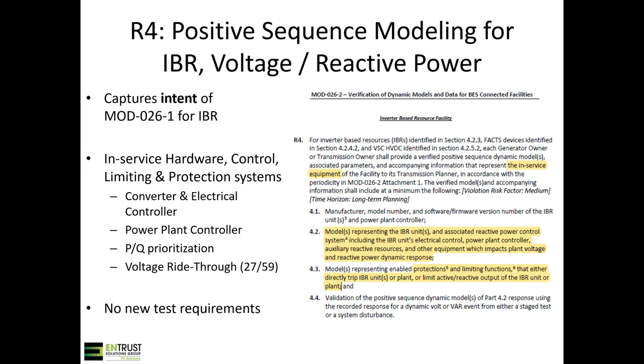Of course, something very pertinent is voltage ride through. We know from numerous events that voltage and frequency settings set to PRC-24 requirements — which the industry has now made very clear, PRC-24 is not defining a trip curve, it's saying don't trip inside, and then follow your capability outside of that — this has reared its ugly head numerous times through different disturbance reports as a root cause. So these are all things we're intending to capture with this new wording, with this specific section for inverter-based resources.